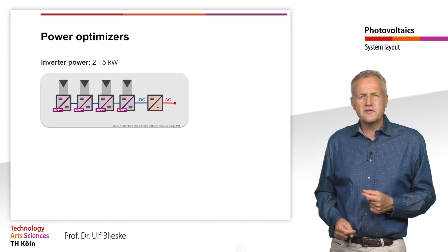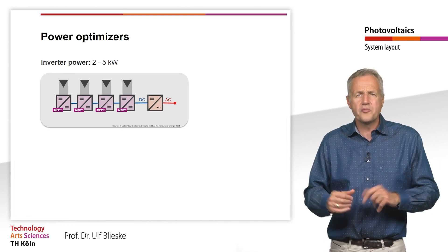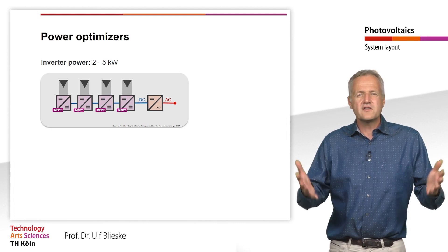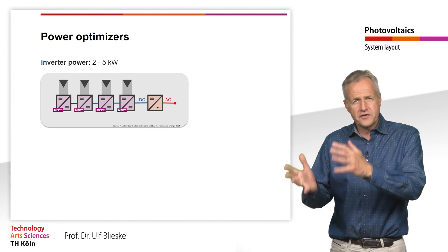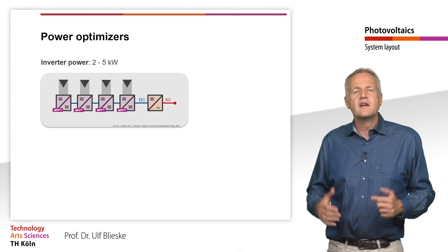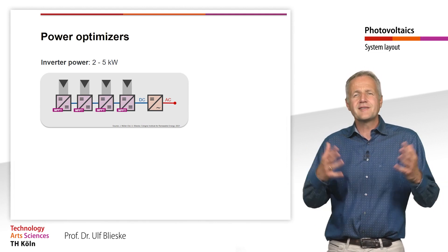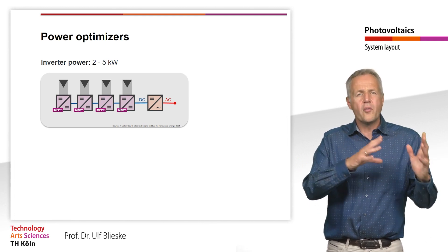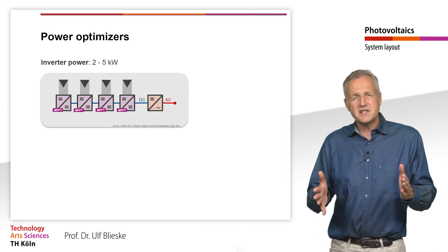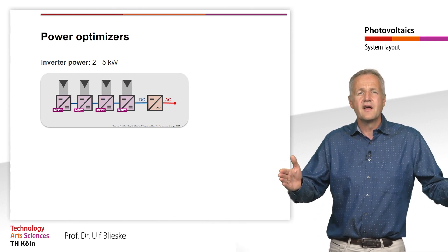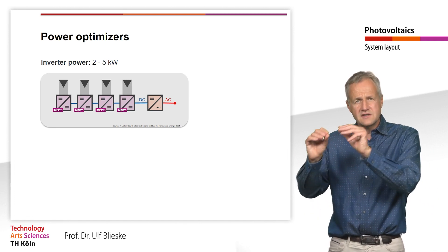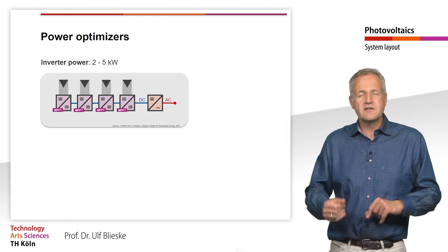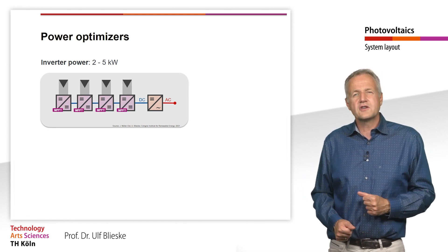An alternative to module inverters are so-called power optimizers, which became more and more popular during the past years. The concept mainly combines the advantage of a string inverter and a module inverter. These power optimizers are basically DC-DC converters. They take over the MPP tracking on module level. The modules with their MPPTs are connected in series, like in a string inverter, and then connected to the DC side of the inverter, in which the MPP tracking has to be deactivated or is not installed from the beginning.